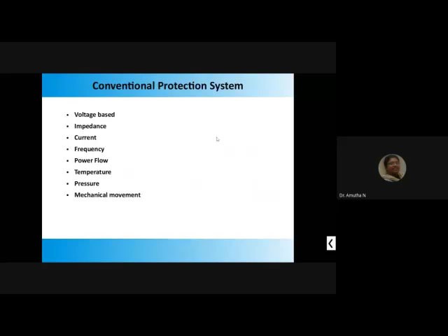But here, apart from the relay characteristics, even though the relay characteristics say that it has to trip at this point, for example between T0 and T1, at the same time it has to observe the grid code, the LVRT or this FRT. FRT is nothing but fault ride through, where the low voltage is assumed as zero. Here, if the voltage is less than V1, it can be disconnected, whereas in the FRT, fault ride through capability, it is a zero voltage condition. Even at zero voltage, the distributed generator has to keep running and supply the power.